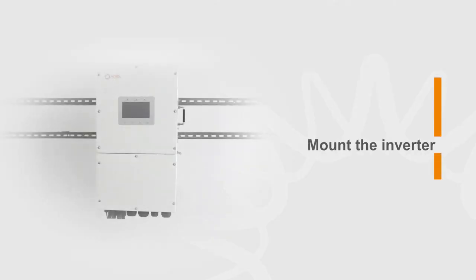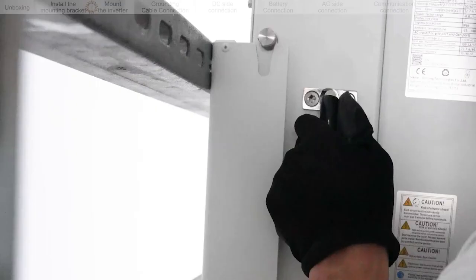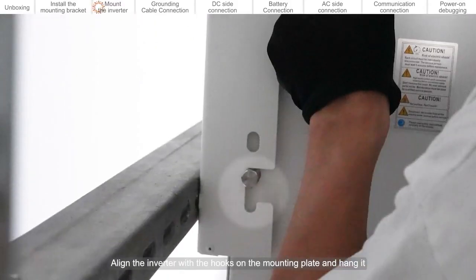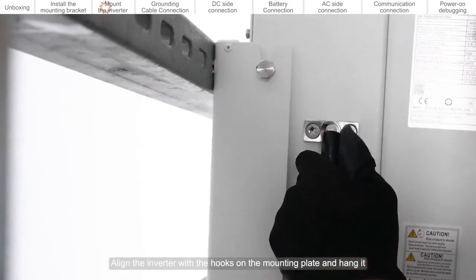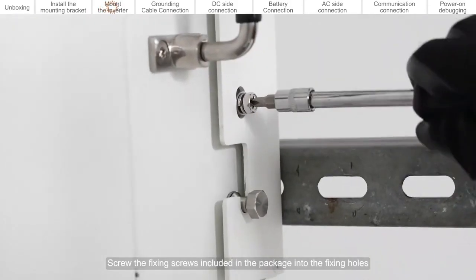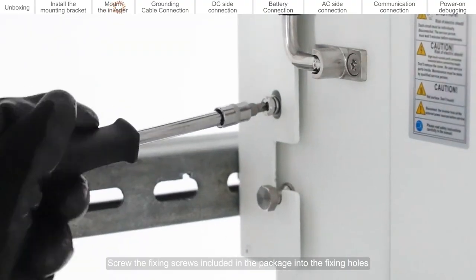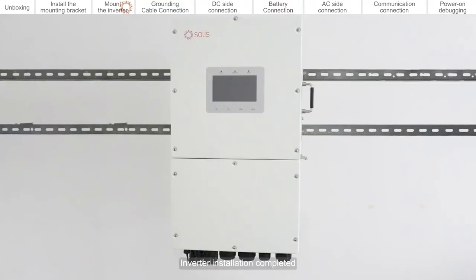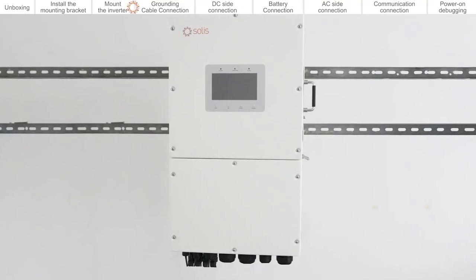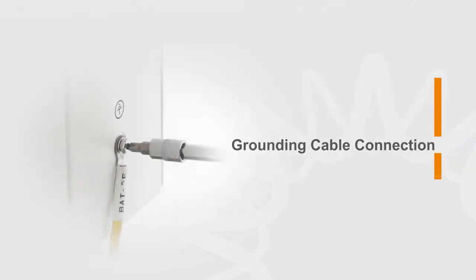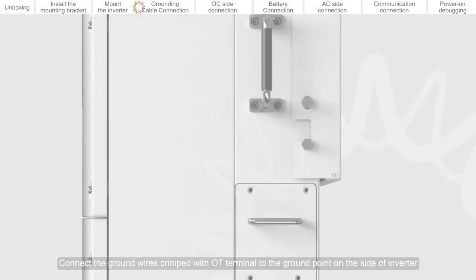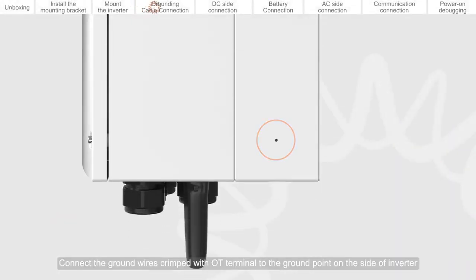Mount the inverter. Align the inverter with the hooks on the mounting plate and hang it. Screw the fixing screws included in the package into the fixing holes. Inverter installation completed. Grounding cable connection. Connect the ground wires crimped with OT terminal to the ground point on the side of the inverter.